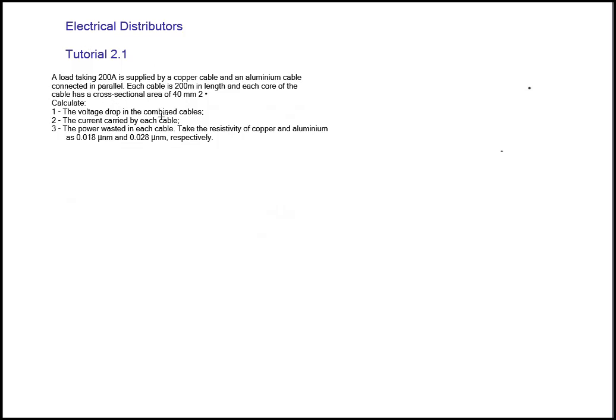Welcome to this tutorial on electrical distribution cables and conductor parameters. We have a load taking 200 amps supplied by a copper cable and an aluminum cable, both connected in parallel. Each cable is 200 meters in length and they both have the same cross-sectional area of 40 millimeters square. We need to find the voltage drop in the combined cable.